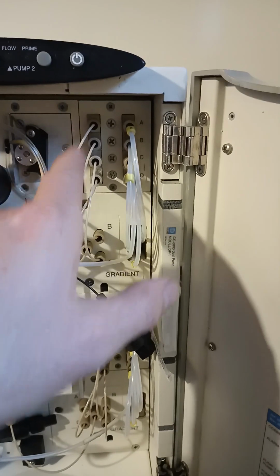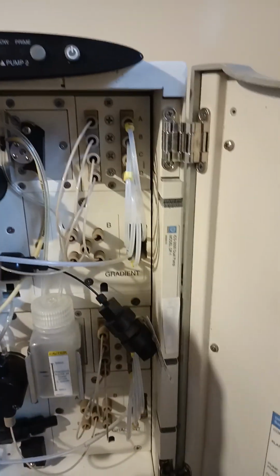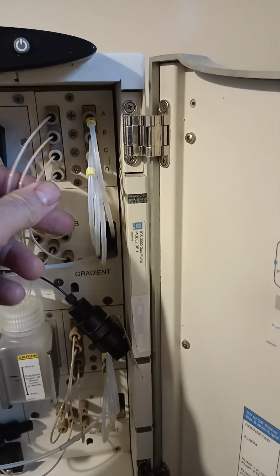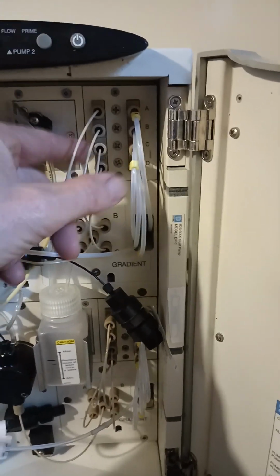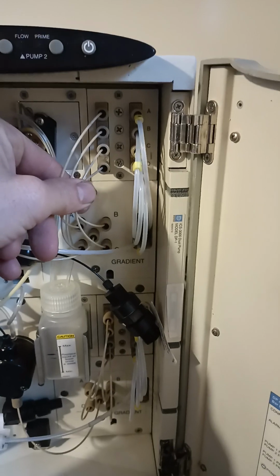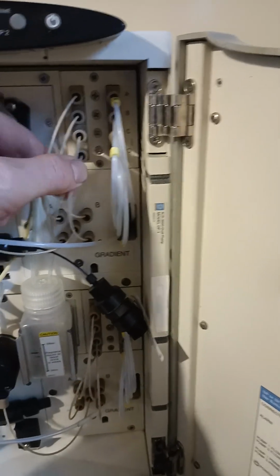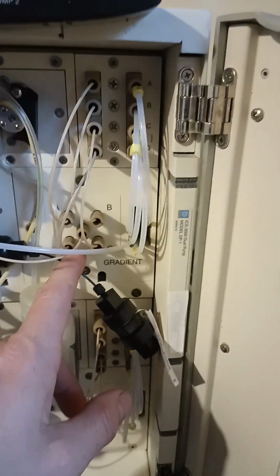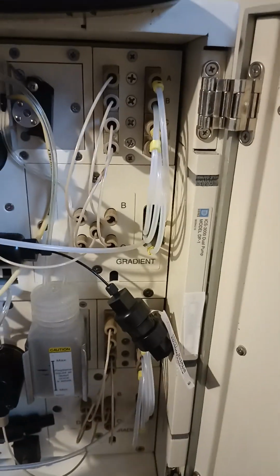But these four go to your eluent bottles, go through a degasser. These are in parallel, but it's only one degasser motor for both pumps. Okay, but these have independent chambers, so the mobile phase doesn't come in contact with each other. And then over to the gradient valve, and the proportioning or gradient valve here leads into the inlet of the pump.